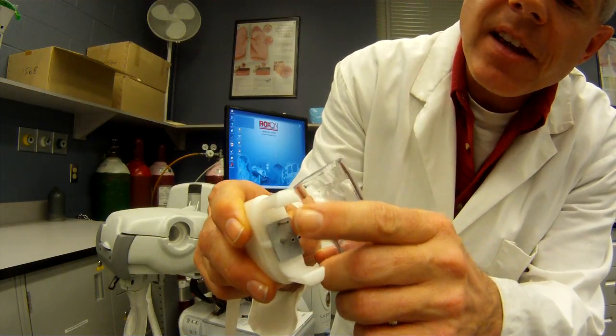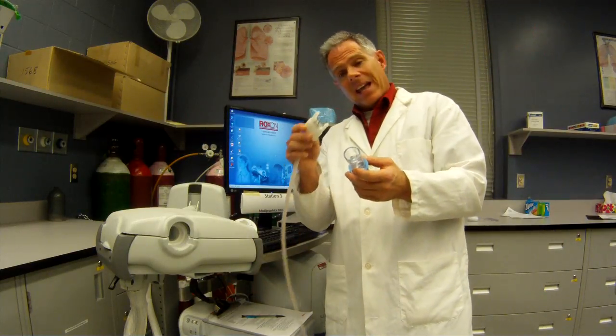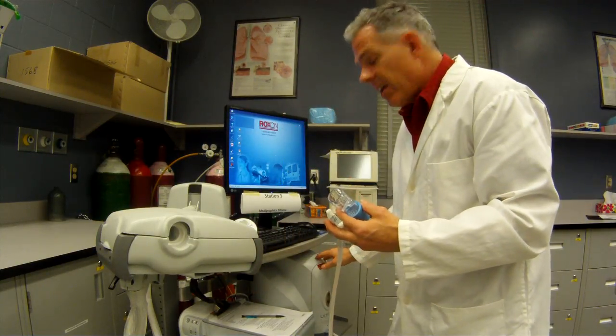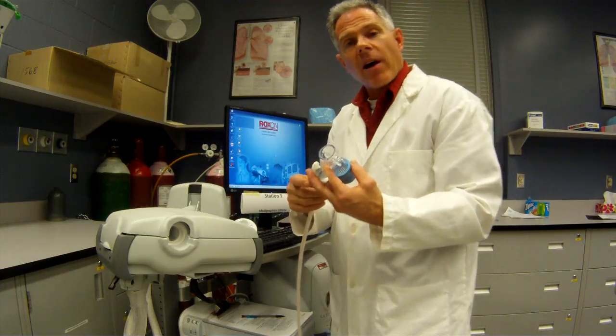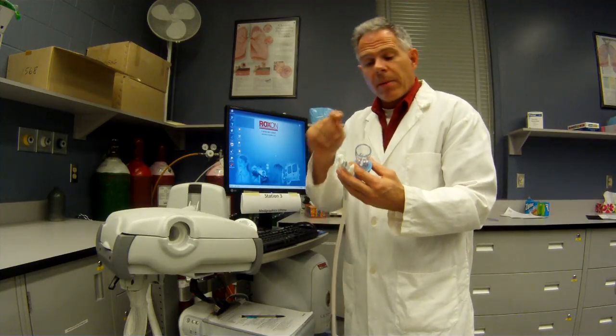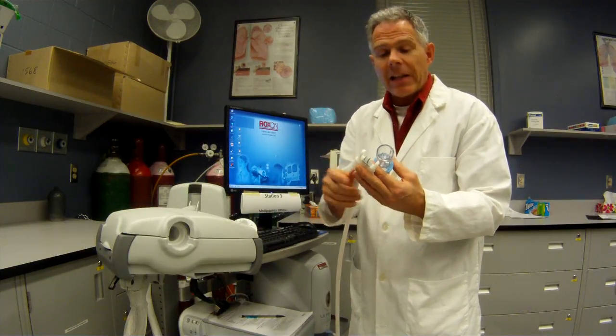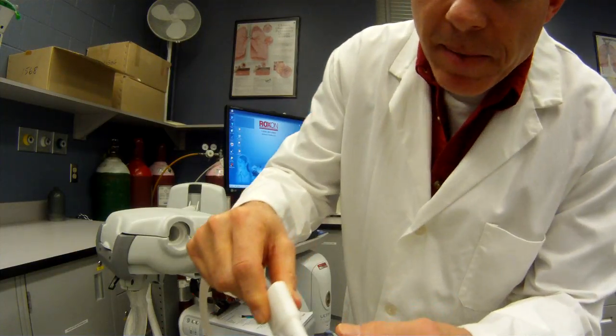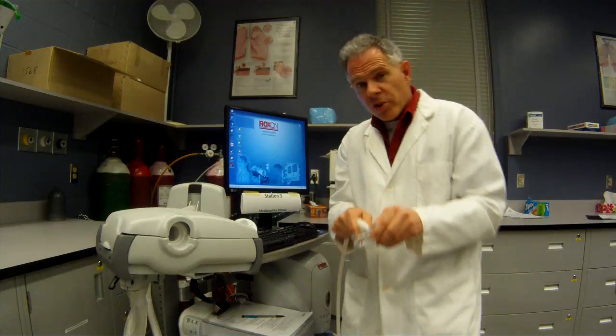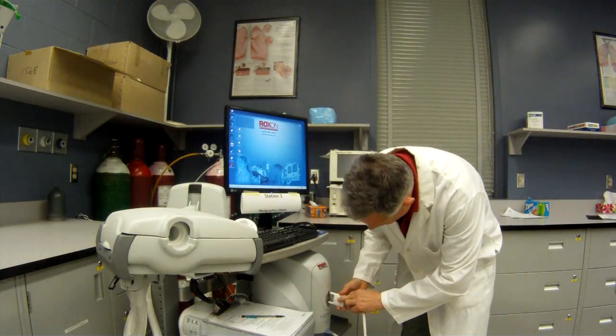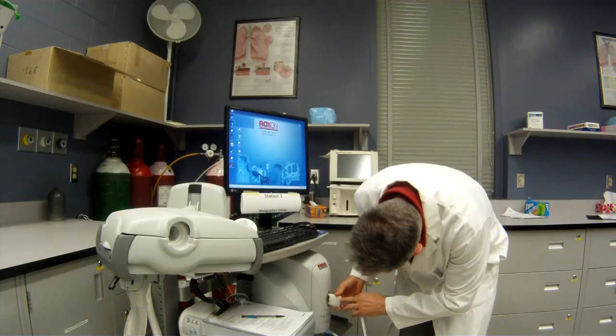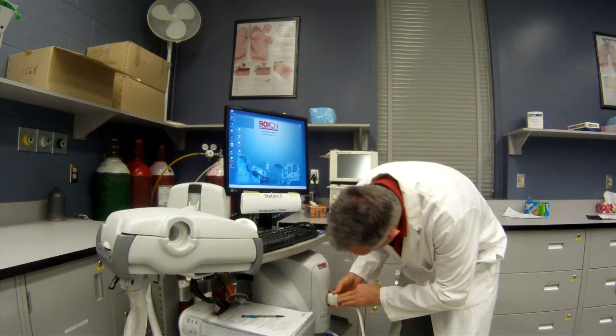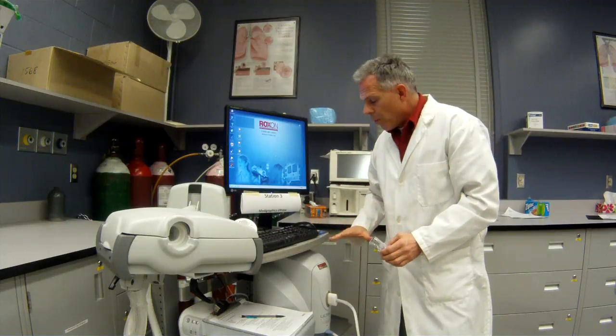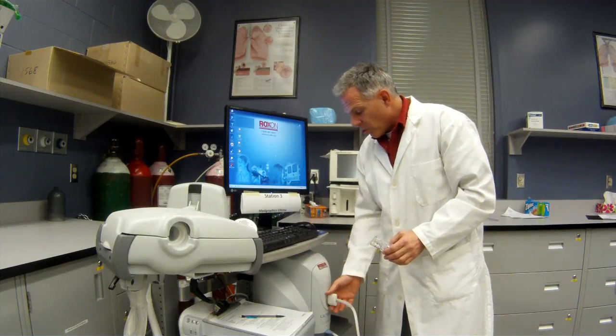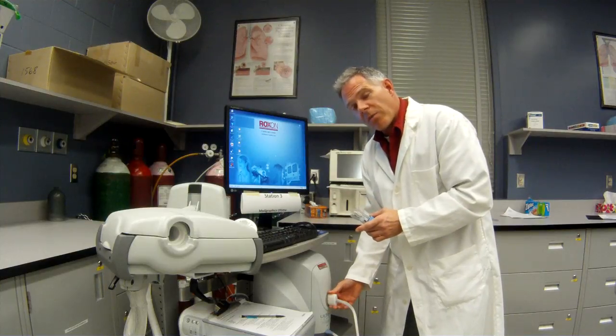This third part here, this other little tiny tube, is for our gas analyzer, and that's hooked up back into here so it can analyze the amount of oxygen or carbon dioxide being exhaled by your patient. For very special tests like the DLCO, it would be measuring carbon monoxide levels as well as helium. So be sure you hook that up correctly. When we're doing a gas calibration, we hook it up just like this to the gas analyzer unit. Be very careful making sure those line up correctly. Your first week or so, you won't be doing any gas analysis, but it's nice to know how that would hook up. Sometimes it'll ask you to do this just before a test.